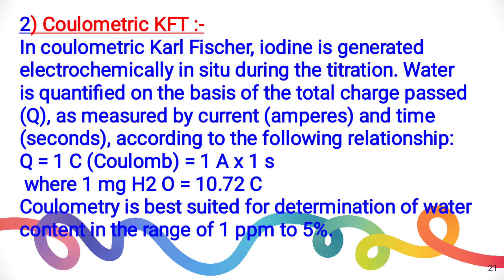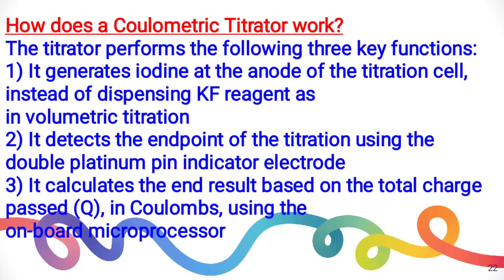Coulometric titration is suited for determination of water content in the range of 1 ppm to 5%. How does the coulometric titrator work? First, it generates iodine at the anode of the titration cell instead of dispensing KF reagent as in volumetric titration. Second, it detects the endpoint of the titration using the double platinum pin electrode. Third, it calculates the end result based on the total charge passed in coulombs using an onboard microprocessor.